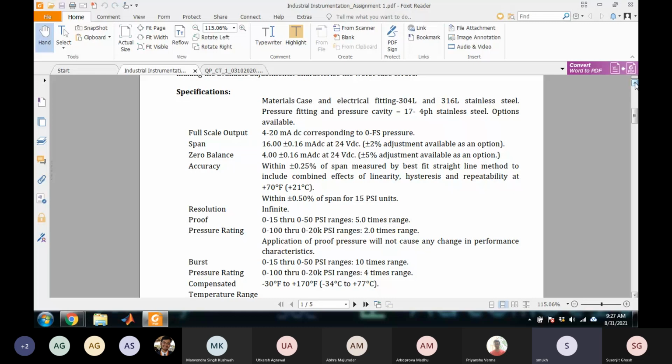So the instrument is supposed to operate at the nominal value of the power supply, 24 volt DC. But suppose you have connected two batteries with 24 volt DC, then if the battery becomes old, that battery voltage will reduce. Does it mean that the instrument will shut off? No. We will see later on, we have not seen the whole specification.